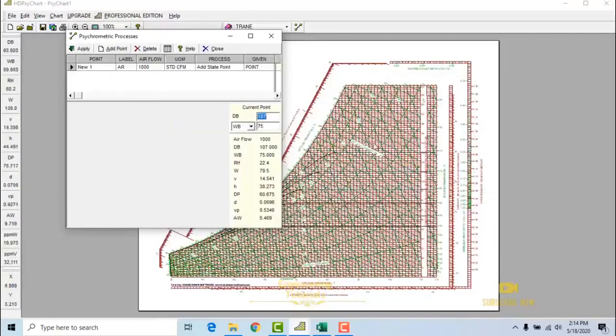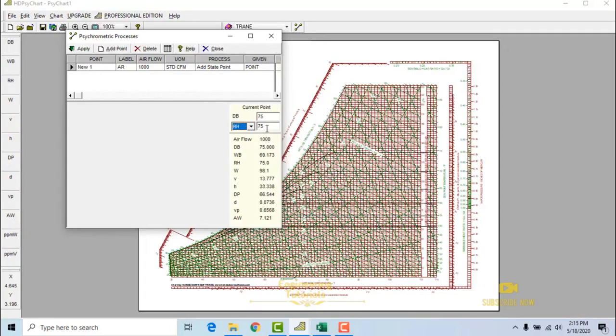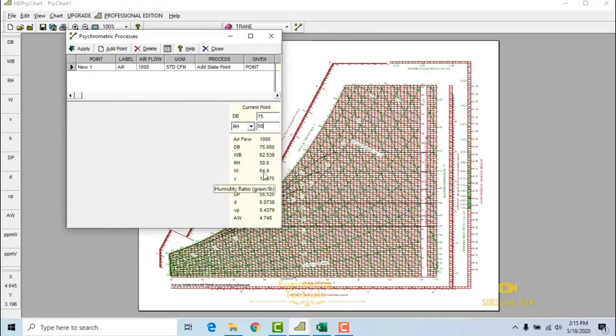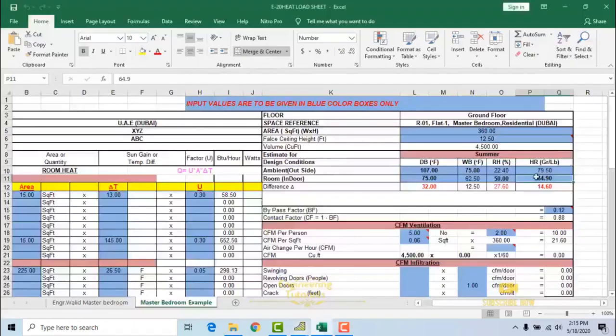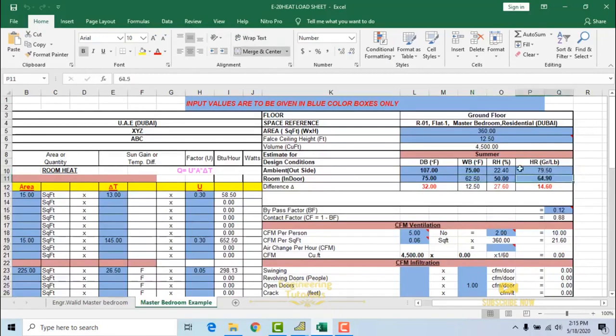So, indoor design dry bulb temperature is 75 degrees Fahrenheit and indoor design relative humidity is 50%. With these two parameters, the wet bulb is calculated as 62.5 degrees Fahrenheit and the humidity ratio is 64.9 grains per lb. As you can see, we have used the same values in our sheet — wet bulb 62.5 and humidity ratio 64.9.